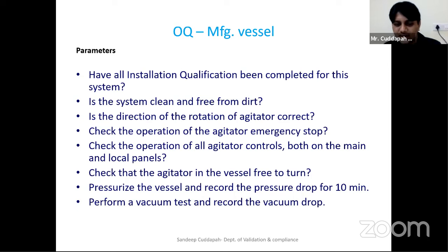Then you have to pressurize the vessel and record the pressure drop for 10 minutes. You give a certain time period and a certain pressure and verify that your vessel does not have any leakage, because this is a manufacturing vessel and we are verifying this test. If you have any other equipment, you will verify for its intended usage whether the equipment is able to meet the requirements or not. You will verify this during operational qualification.